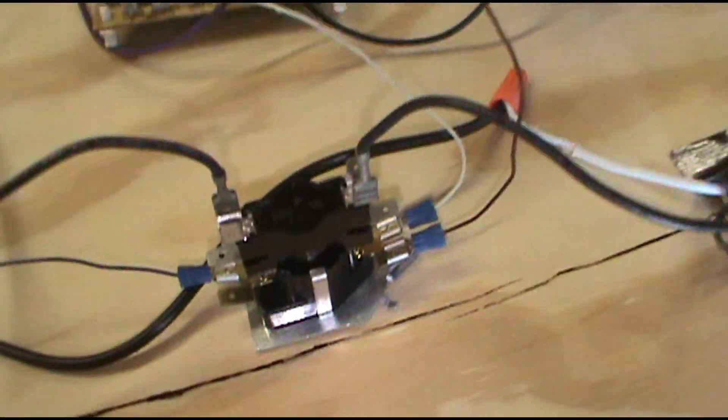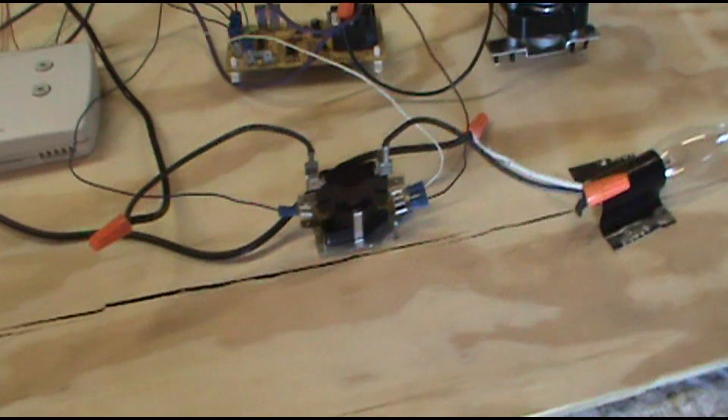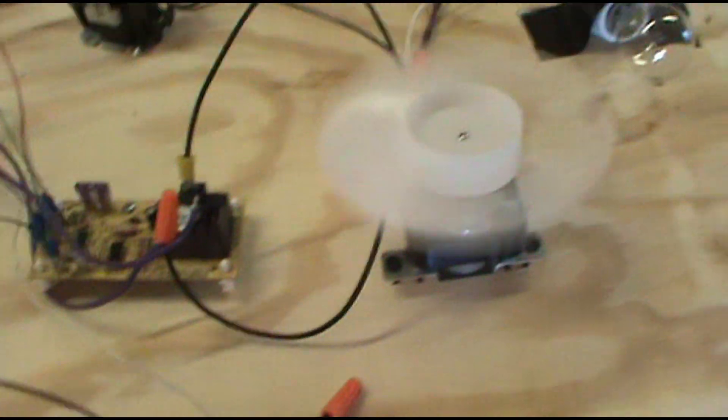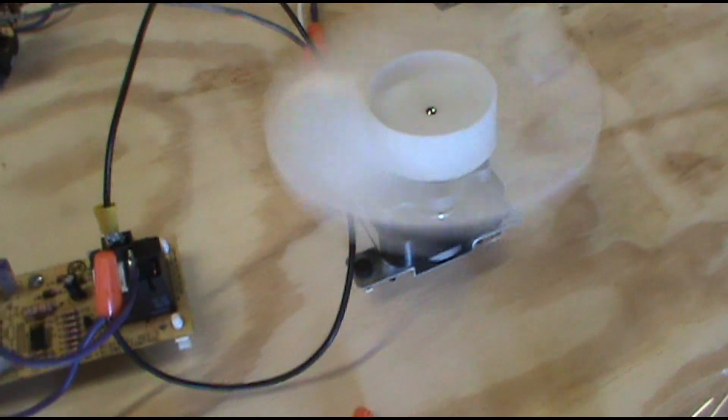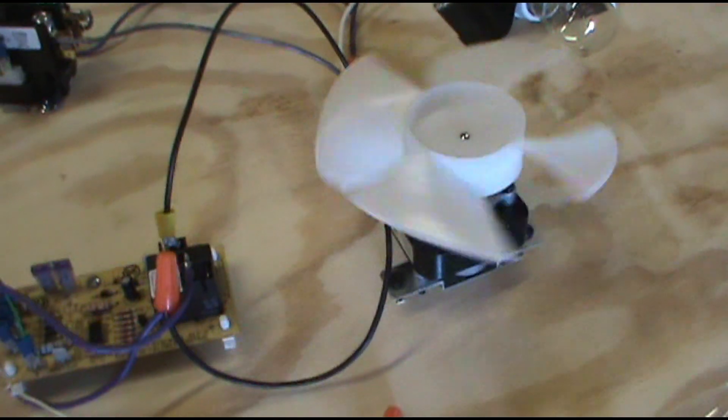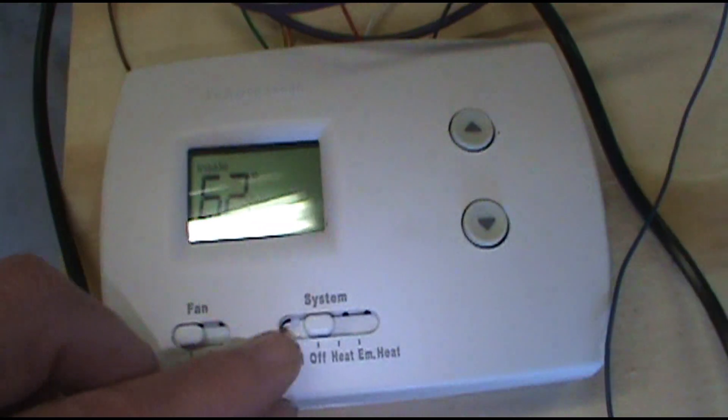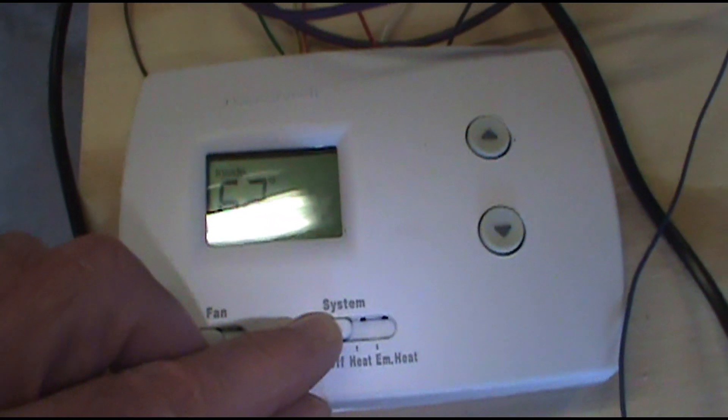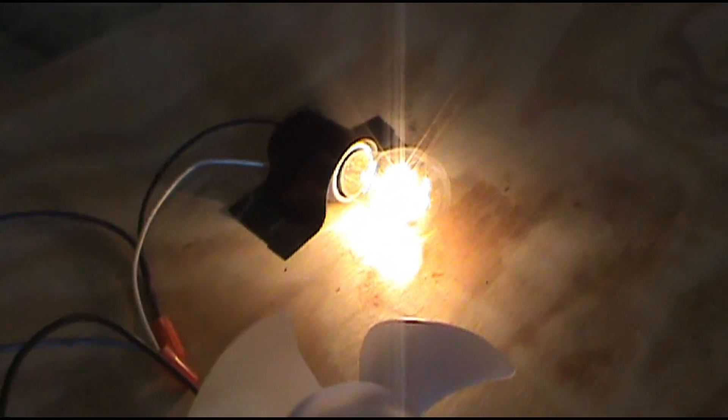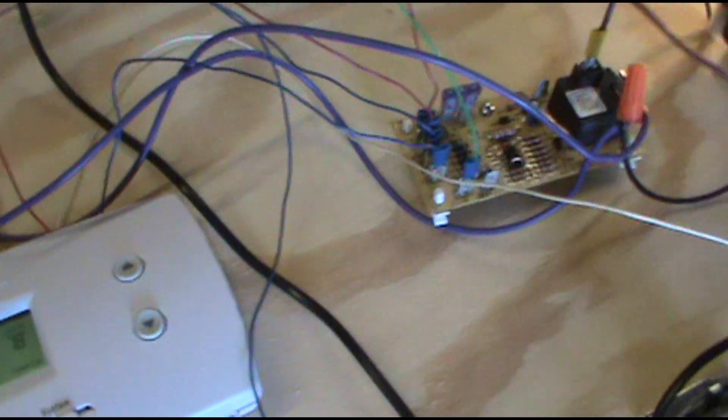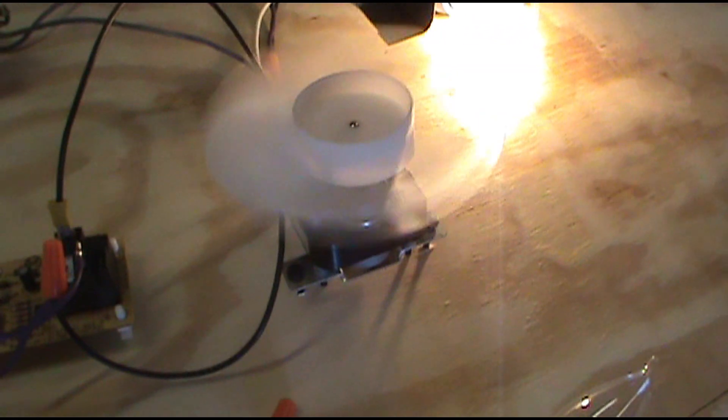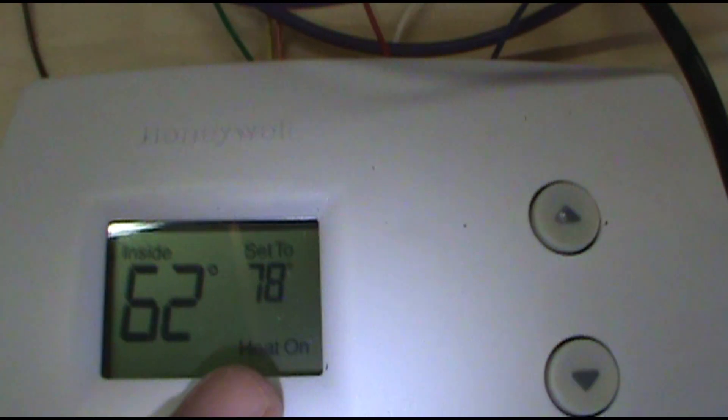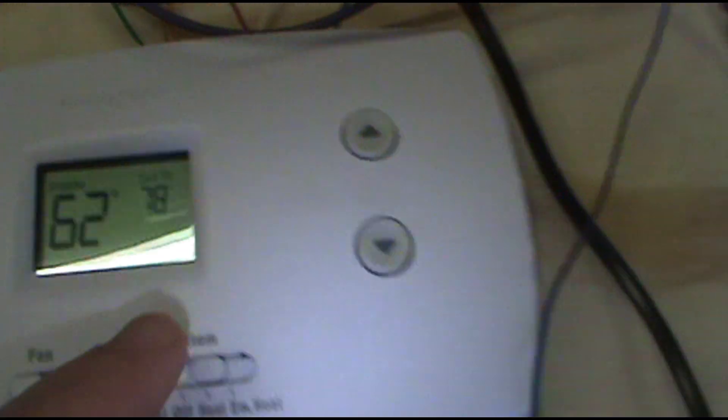Got the sequencer. I've been probing around on this thing with my meter trying stuff out. There we go, it's got a little bit of delay on it just like it does out in the field on the units. Now we'll go to heat. There we go, condenser's on, fan's on. Now since we have it set way up, the auxiliary heat is going to come on and that's going to kick on our heat strips.